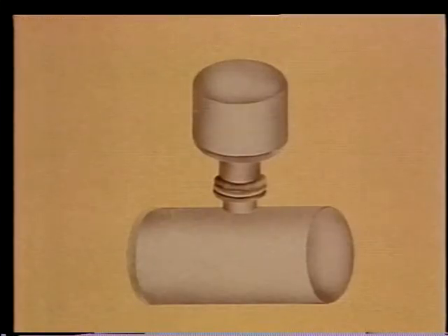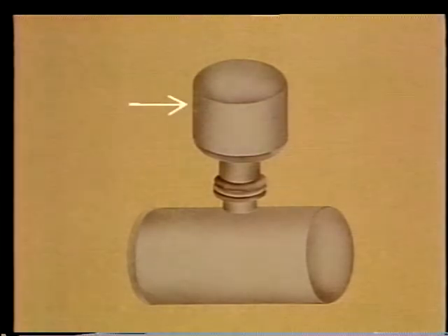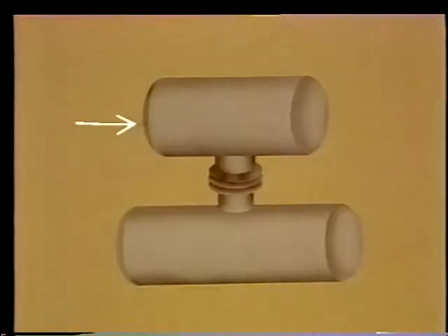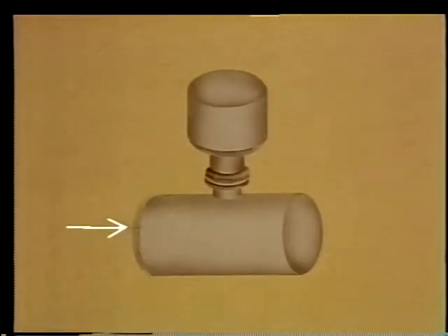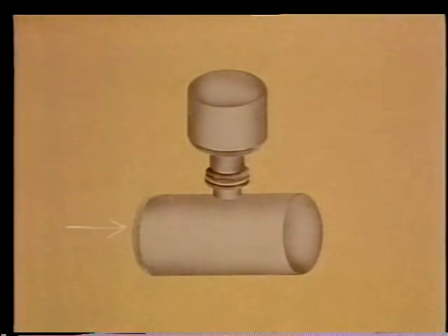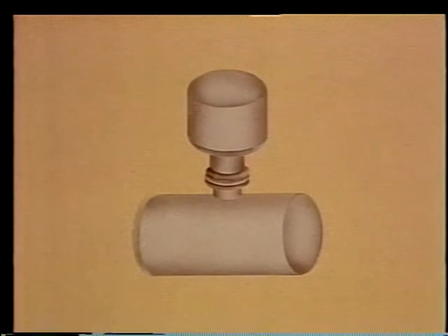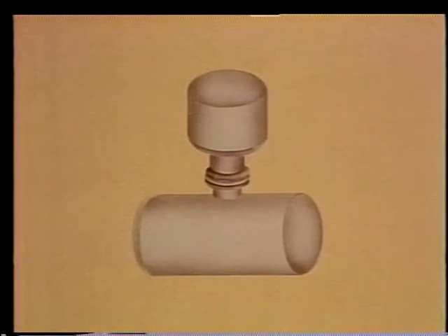This gets rid of air and gases that are trapped in the feed water. Just like a shell and tube heat exchanger, the direct contact heater may have a vertical shell or a horizontal shell and the storage tank may also be vertical or horizontal depending on design requirements. On the inside, a direct contact heat exchanger can be one of three basic designs: spray, tray, or a combination.